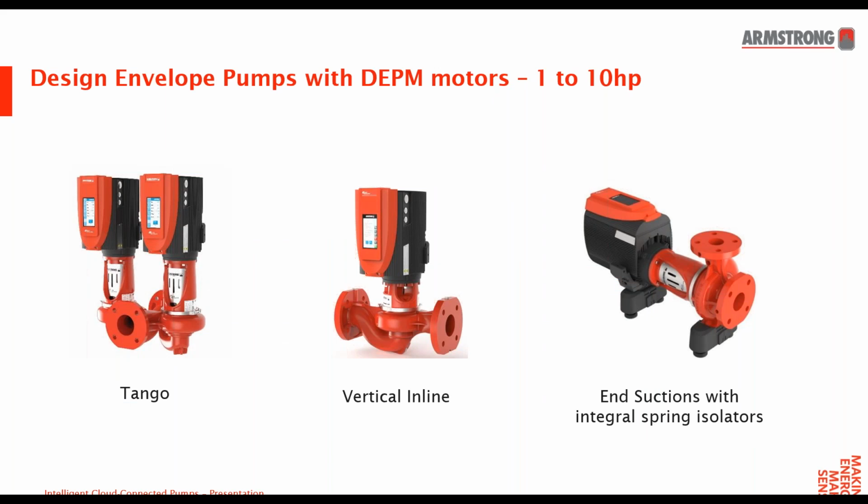And design envelope pumps with DEPM motors right now are available up to 10 horsepower in our Tango series, which is the dual pump series, as well as vertical inline pumps and our end suction pumps with integral spring isolators. So these built-in spring isolators allow you to eliminate an inertia base.